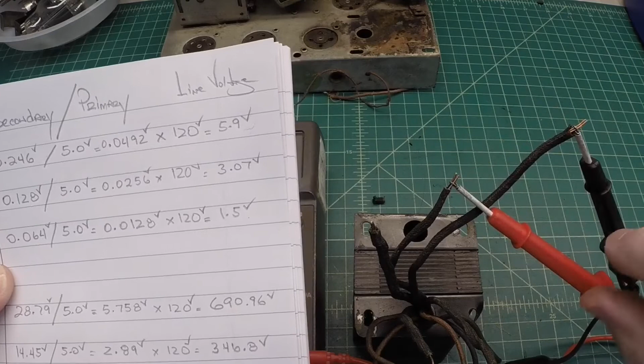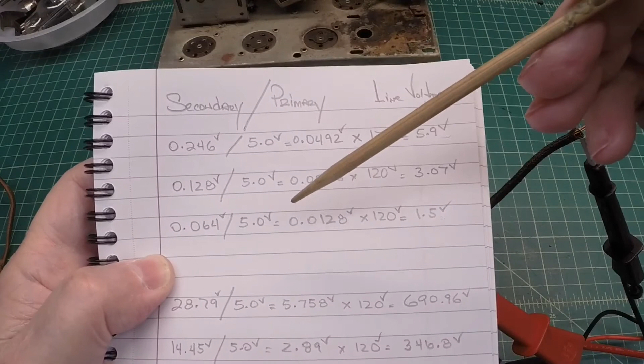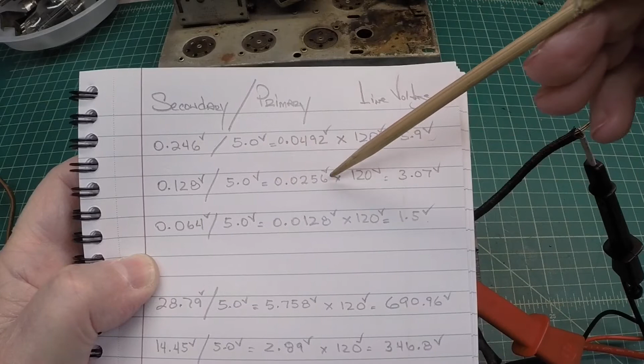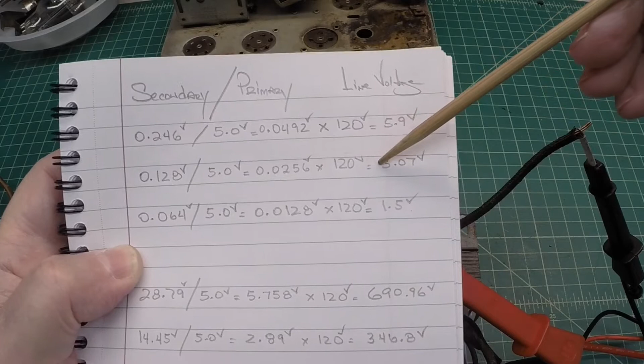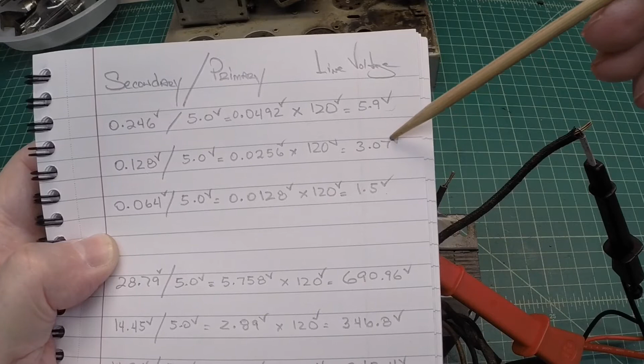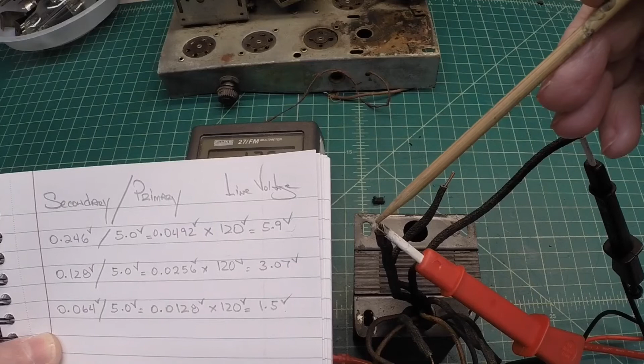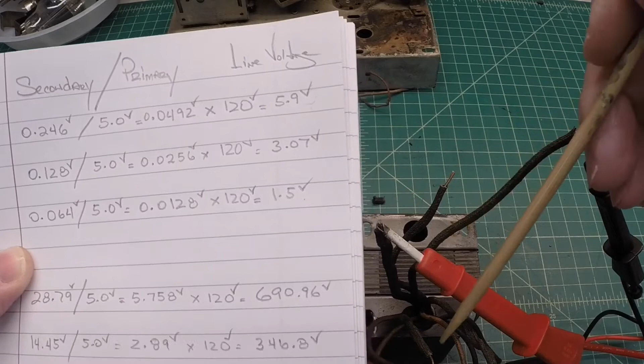If I move over to this location, you can see on the meter I'm reading 0.125, just like a bit ago when I did the same exercise and read 0.128. Dividing that by 5 comes out to 0.0256 volts, and multiplying that by 120 gives me around 3. So I think this is the tap actually used in the radio, not this other one, because if you look at the heater voltage requirements for the tube, it's 2.5 volts, and again this is without load.